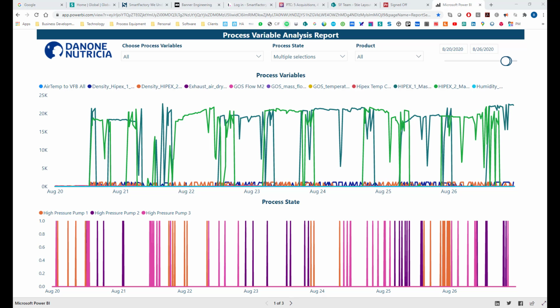All of our raw data that we have in WAPS is being pushed into the Power BI dashboard. But Power BI is not fast enough for the type of data that we're dealing with, so it's really useful for historical trending analysis. For example, we're taking air temperatures and logging them every second, but in Power BI, we're averaging them over 15-minute intervals.